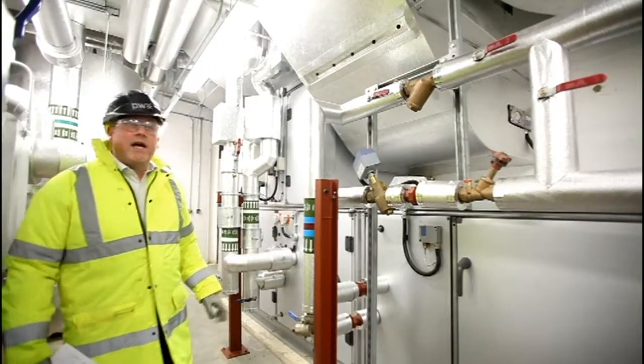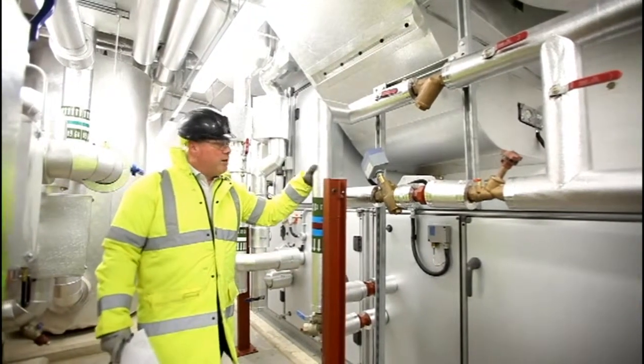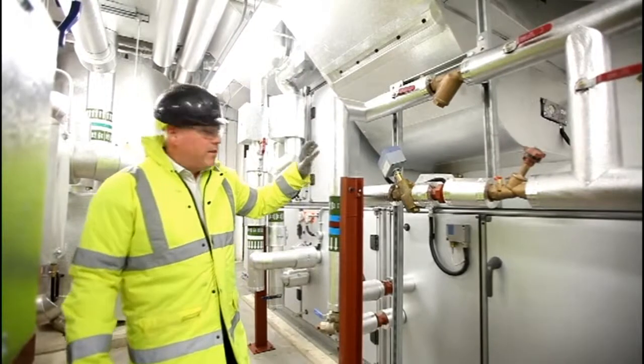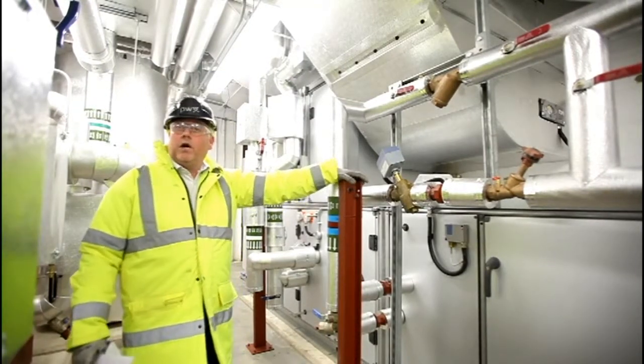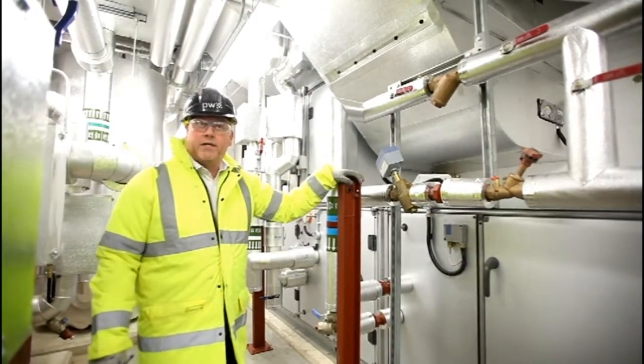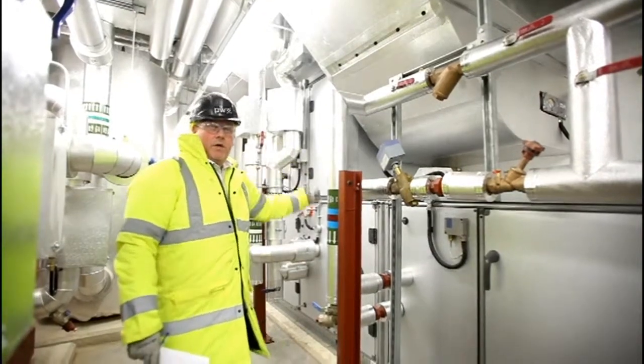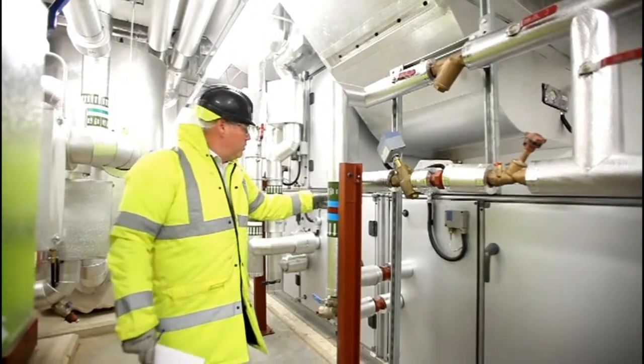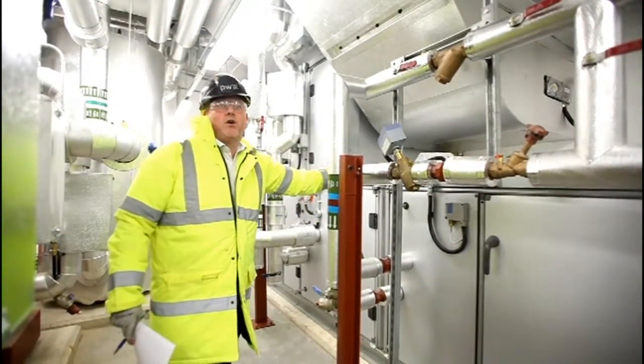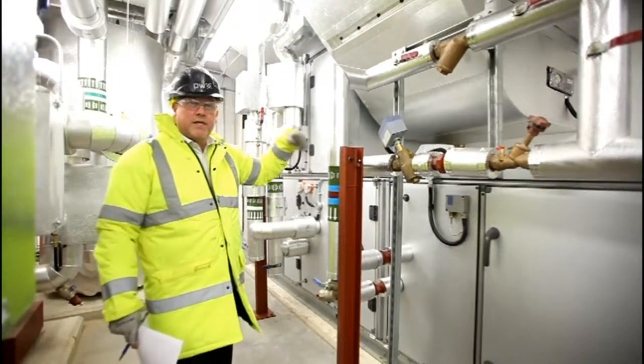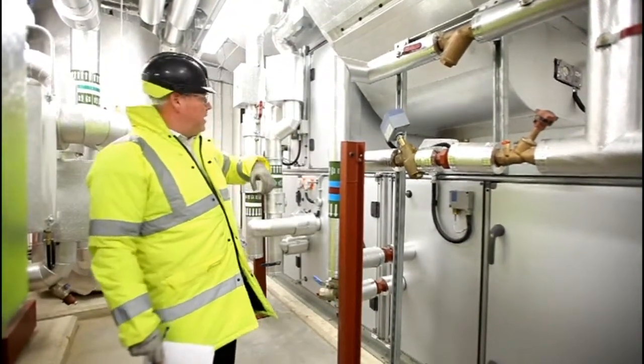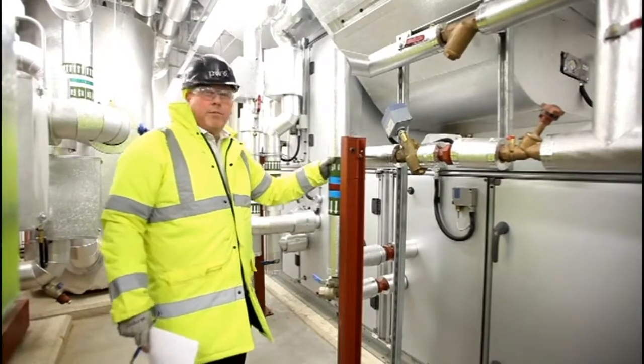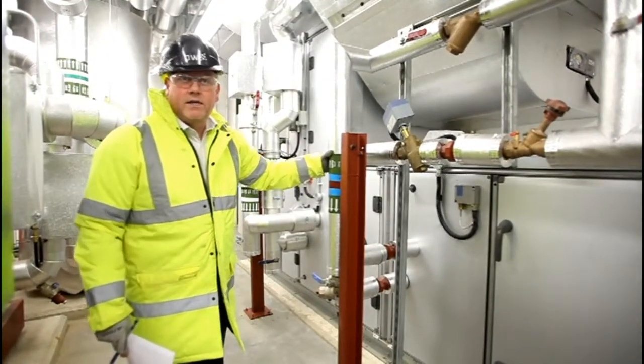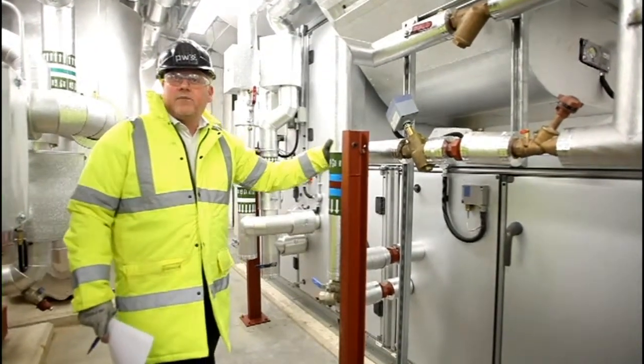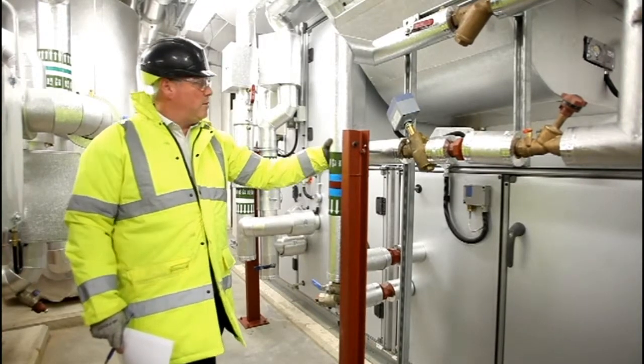We have a return air system. So what we try to do to make it more efficient, we take the warm air from the spaces, or in the summertime the cool air from the spaces, and recirculate it and reuse the air. So we try to gain a bit of what we call free cooling or free heating. So we use the space temperature in there, so potentially it basically means that the boilers don't need to work as hard as they would normally, and the same with the chiller, it doesn't need to work as hard as normal.